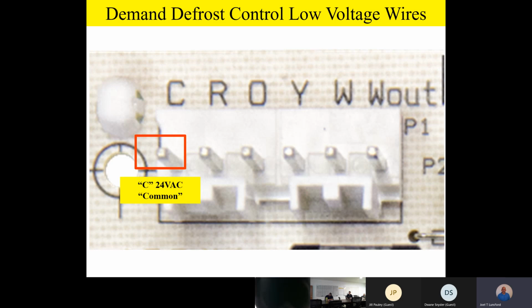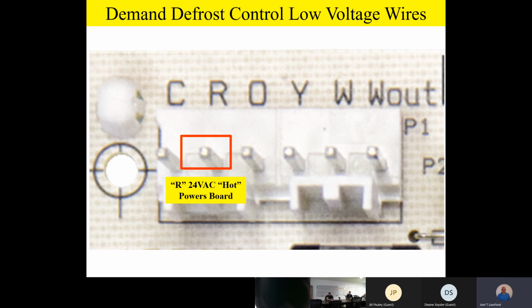Now remember, team, the demand defrost control has to have power to it all the time for it to function. So even in the dead of summertime, when it's in the cooling mode, it doesn't matter. It's still monitoring those sensors, and it still needs power to that board on C and R year round. So again, C is 24-volt common. Right next to it is our R, which is our 24-volt hot that powers the board up. And one more time, remember, this board has to be powered up year round.